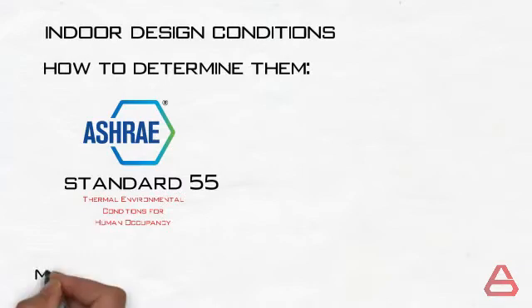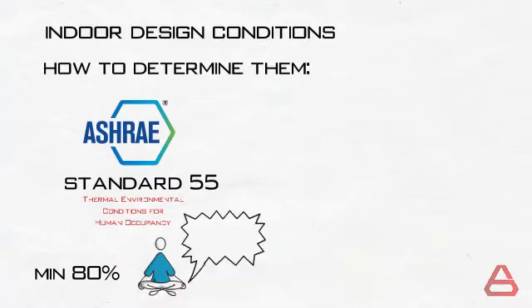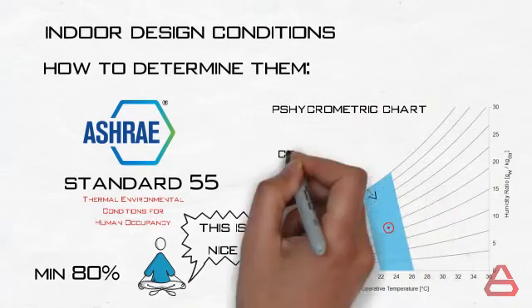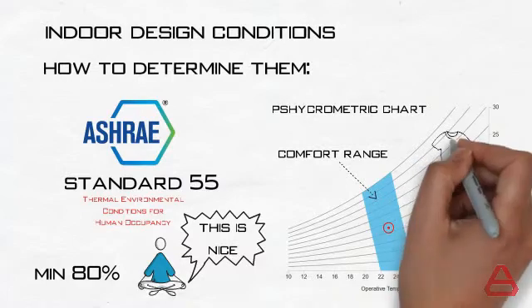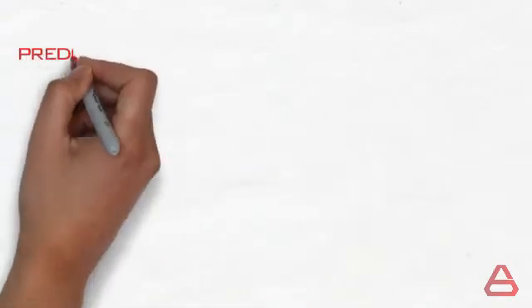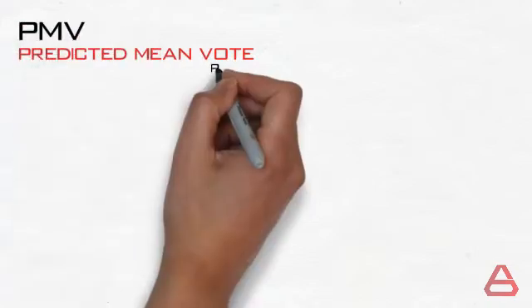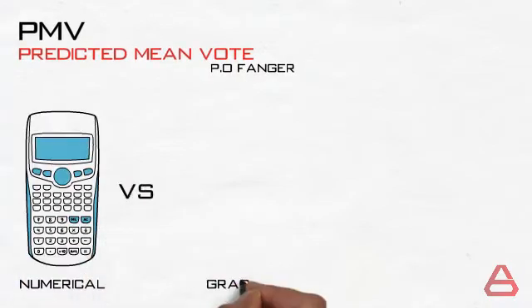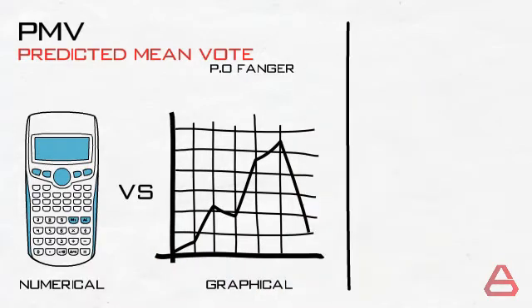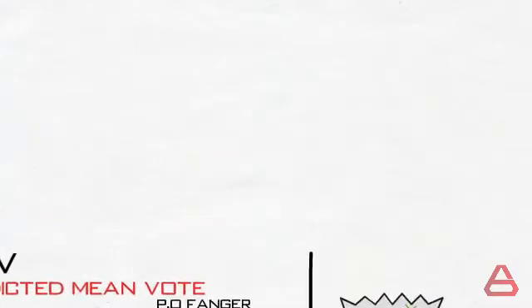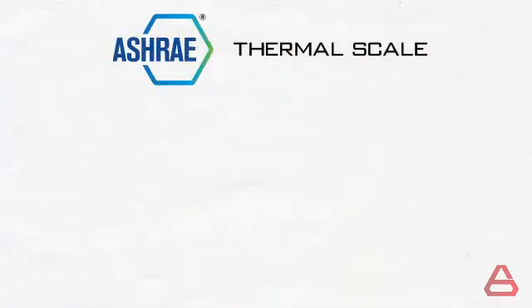The standard demands that at least 80% of a large group of people find a certain environment thermally acceptable. Through research and experimentation, ASHRAE was able to produce a graphical method that provides the range of acceptable operative temperatures and humidity with corrections for clothing and activity. In addition to the graphical method, one can also use the Predicted Mean Vote method, PMV, created by P.O. Fanger. The PMV method provides a more numerical approach instead of a graphical one.